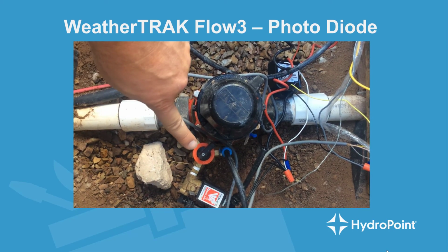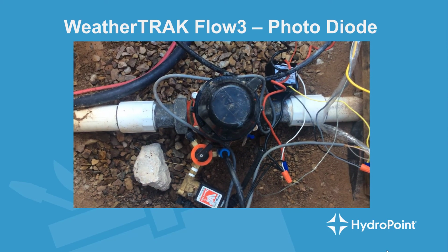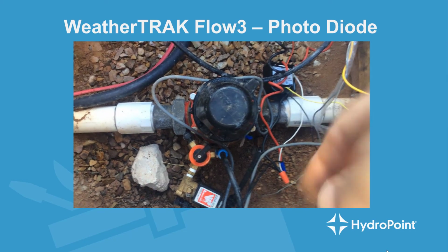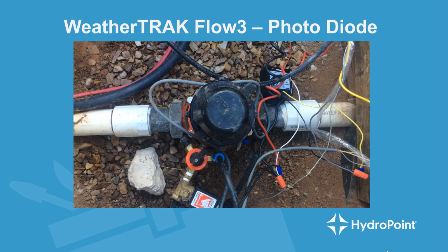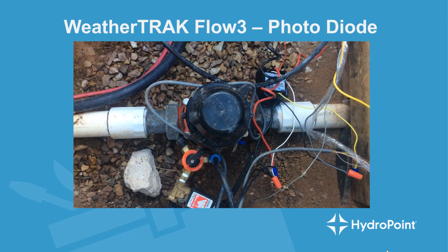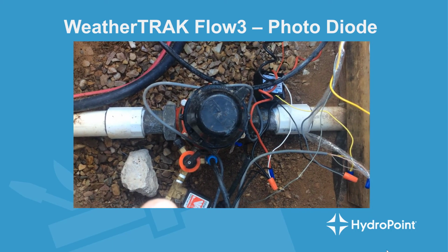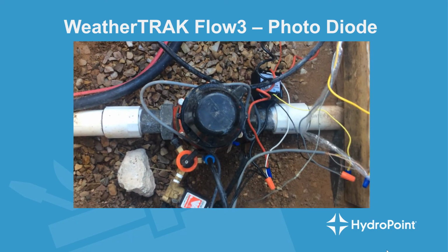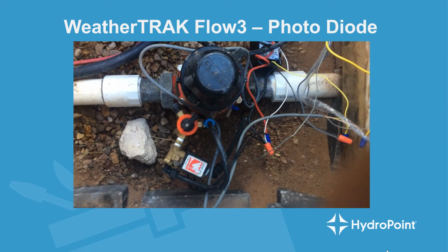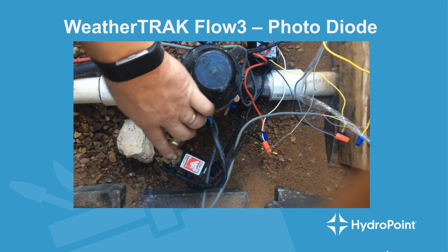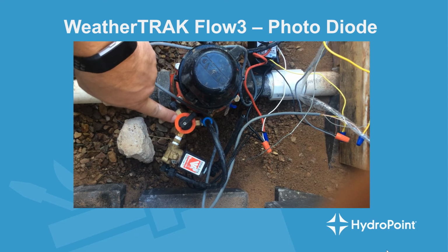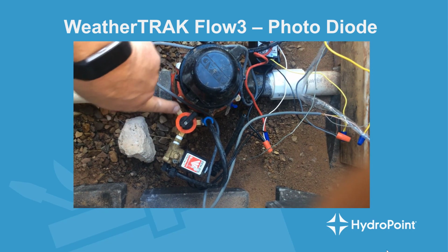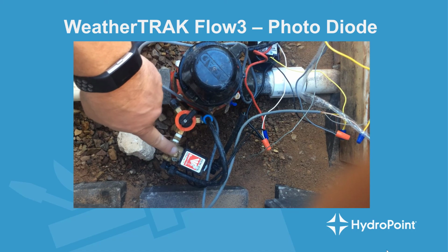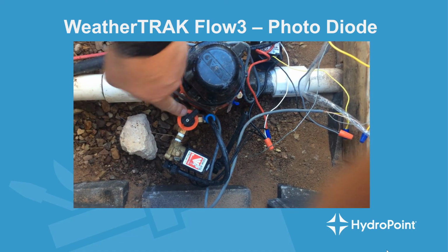Over here we have the three-way selector switch. There are 3 different positions on the dial, and you can either have it on open, closed, or auto. And auto is the position that you want if it's running from the controller. And then down here we have the solenoid selector switch, and it can either face the solenoid or face the three-way selector switch. We always want the solenoid to face the three-way selector switch. This is the activated position, so make sure that this little guy is facing the three-way selector switch.